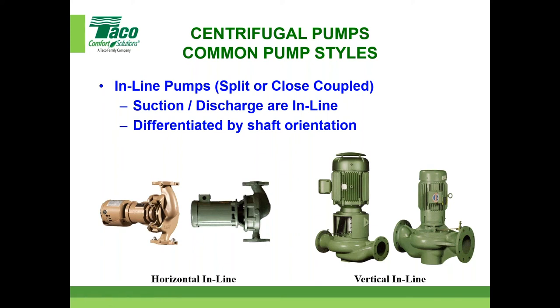But one thing that I like to mention, and these have instruction sheets as well. I apologize, I didn't put them in the handouts, but now that you know how to go get them, you can go see them yourself and read them. They recommend, actually, it's not a recommendation, it's a requirement that these motors are not supported in the field. And I'll tell you, you go into a mechanical room, you'll see these with a channel bar underneath it and some rods sticking up and supporting that. And same thing maybe on these.